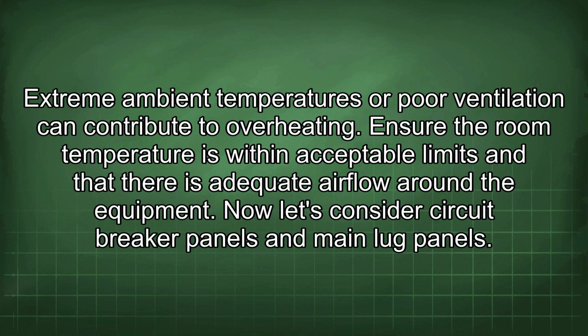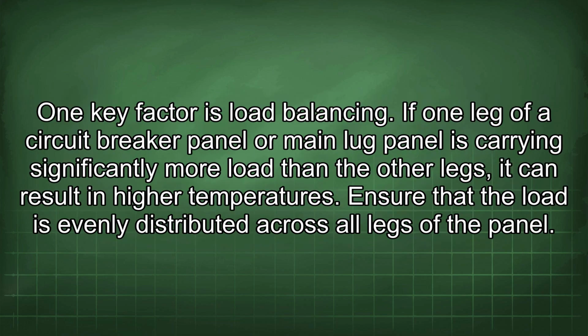Now let's consider circuit breaker panels and main lug panels. One key factor is load balancing. If one leg of a circuit breaker panel or main lug panel is carrying significantly more load than the other legs, it can result in higher temperatures. Ensure that the load is evenly distributed across all legs of the panel.